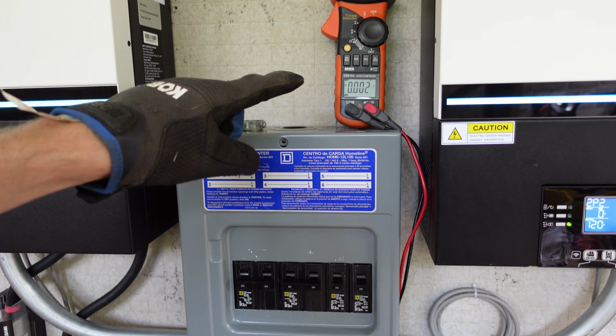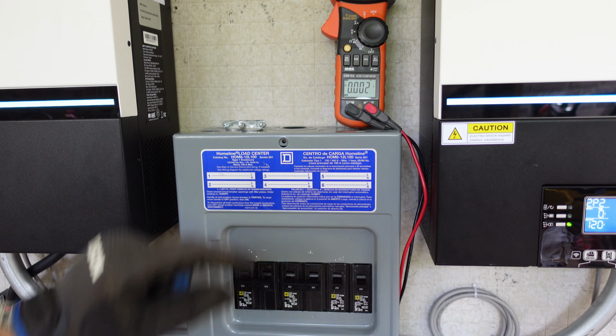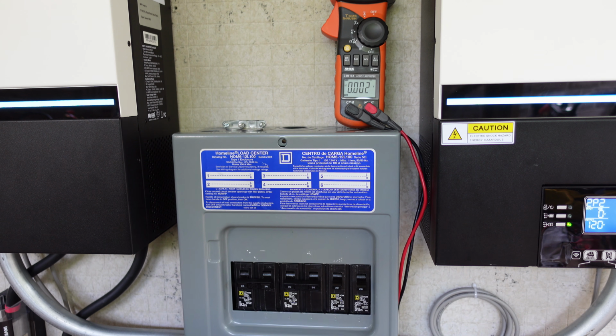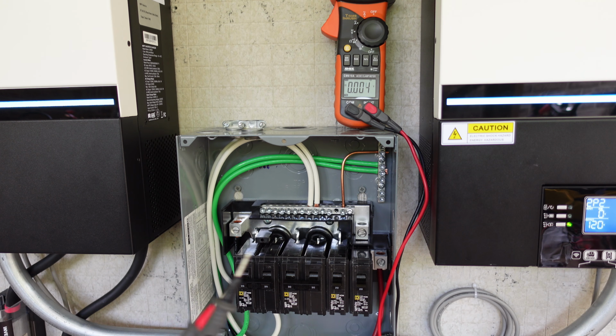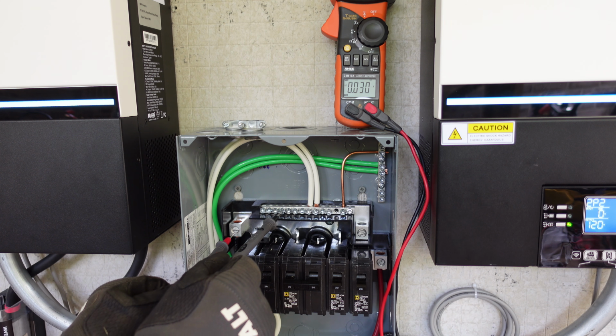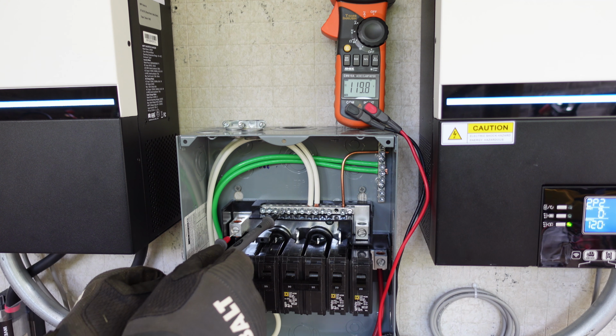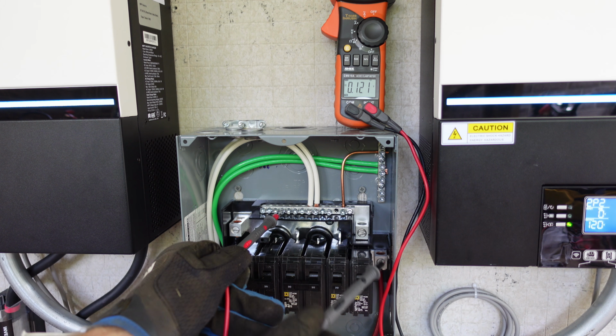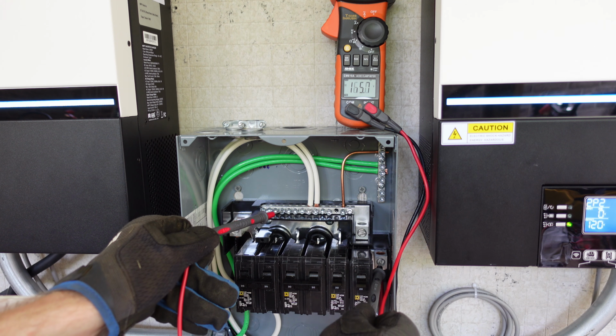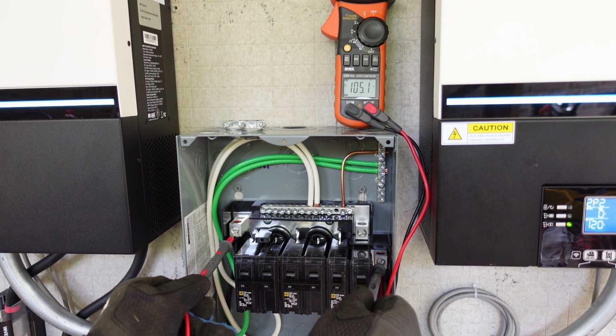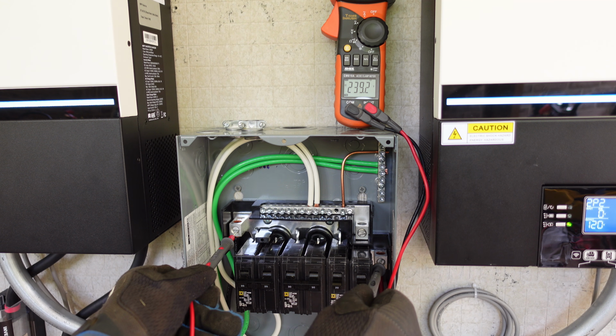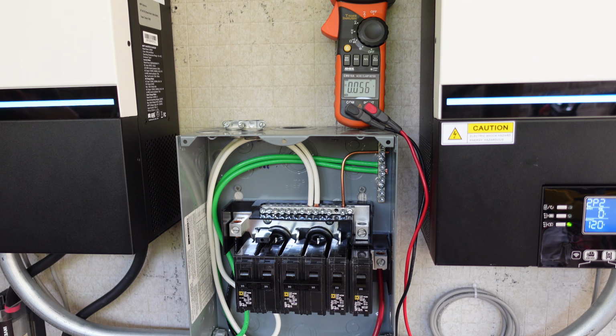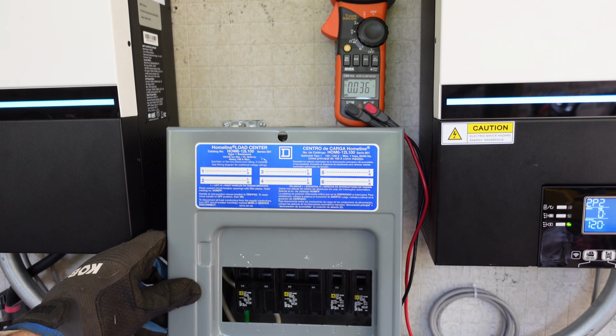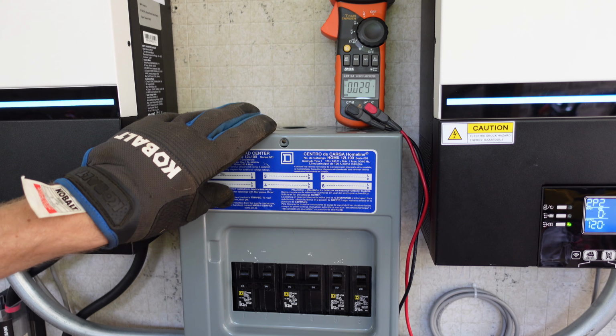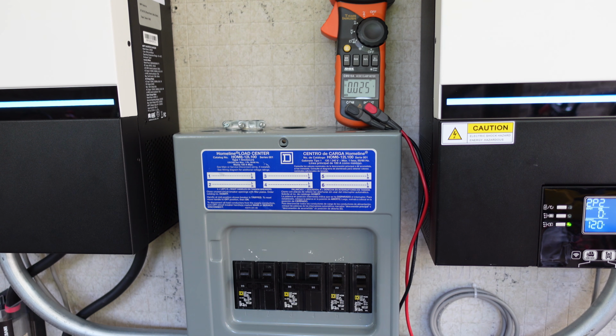Alright, so now I've got my voltmeter up here. It is set to AC. I'm going to very carefully check this panel and make sure it's working as expected. So from neutral to black I should see 120. From neutral to red I should see 120. And from red to black, I should see 240. So those voltages are perfect. I'm now going to return my cover and never stick my hands in there again while this is turned on.